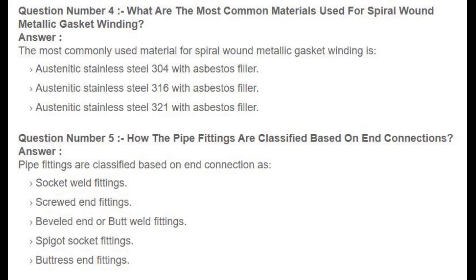Question number 4: What are the most common materials used for spiral wound metallic gasket winding? Answer: The most commonly used materials for spiral wound metallic gasket winding are austenitic stainless steel 304 with asbestos filler, austenitic stainless steel 316 with asbestos filler, and austenitic stainless steel 321 with asbestos filler.